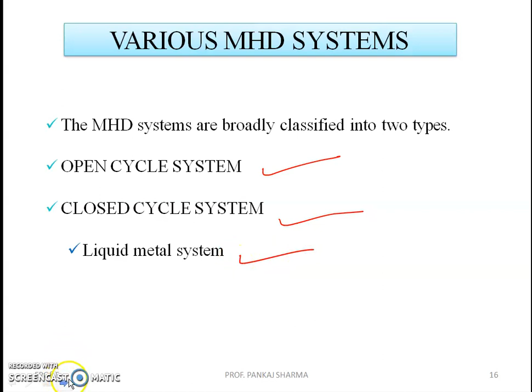In the open cycle system, the fuel used may be oil through an oil tank or gasified coal through a coal gasification plant. The fuel, that is gasified coal, oil or natural gas, is burnt in the combustor or combustion chamber as seen in the previous block diagram. The hot gases from the combustor are then seeded with a small amount of ionized alkali metal, that is cesium or potassium, to increase the electrical conductivity of the gas.